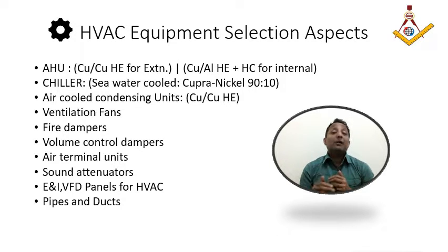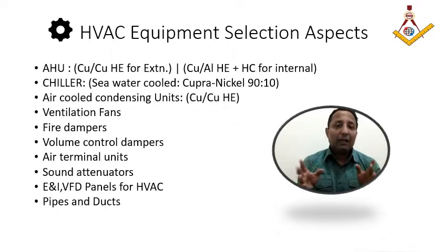But in case the water cooled facility is not available, say for example there are standalone platforms. There are platforms which don't have an accommodation. It consists of only an electrical room. In that case, water provision is not there because there is no water required for anything. So the last option that prevails is the air cooled system. In that case, they go for a large capacity air cooled chiller, or mostly an air cooled condensing unit and AHU arrangement is provided.